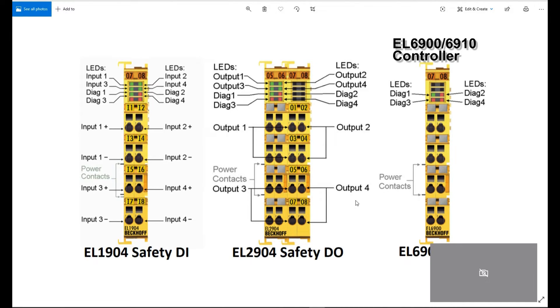But keep in mind — I found one problem. This picture comes from the back of the TwinSafe manual. However, I found that the pin numbers shown in the picture are wrong. The correct pin numbering sequence from TwinCAT cards goes 1, 2, 3, 4 on one side and 5, 6, 7, 8 on the other side. The numbers shown in that manual picture are not correct.